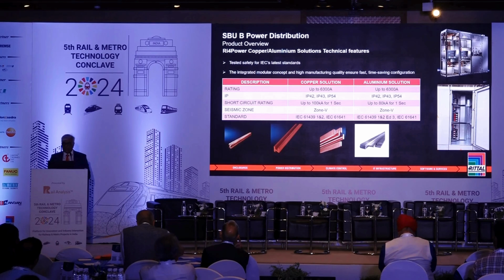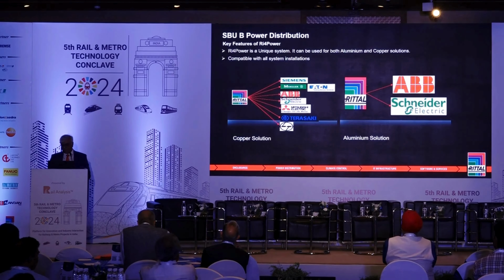And of course, our containment also meets IEC 61641. If we talk about the aluminum solution, here also we can go up to 6,300 amps, IP54, 80 kA for 1 second. But here we have IEC 61439, part 1, part 2, edition 3, which is the latest edition for the aluminum solutions. So the USP is that our system is certified with all the switchgears, meaning it is switchgear independent.